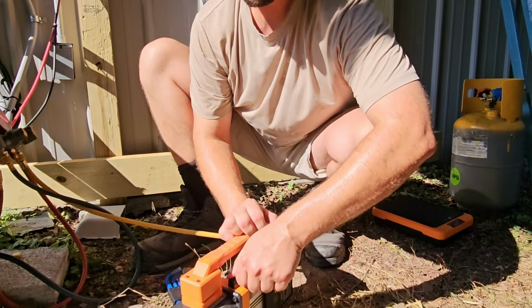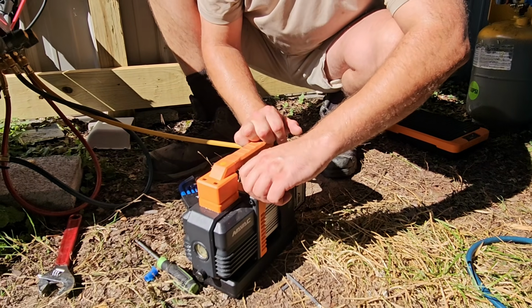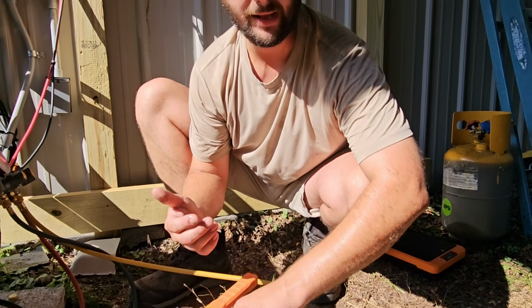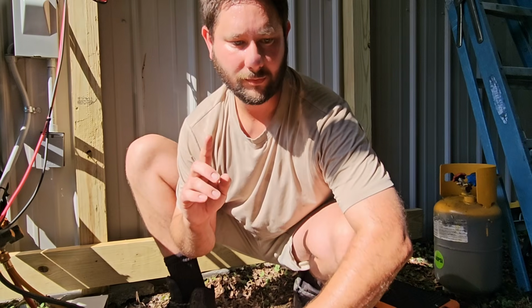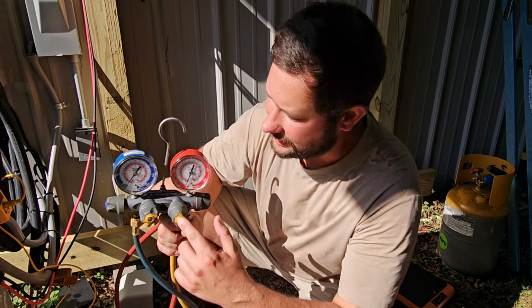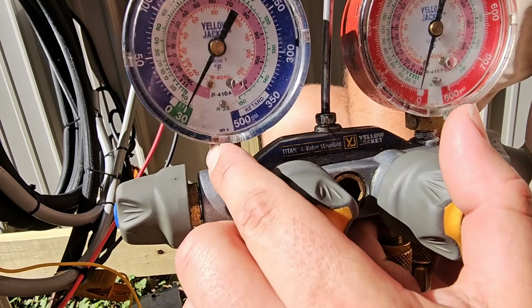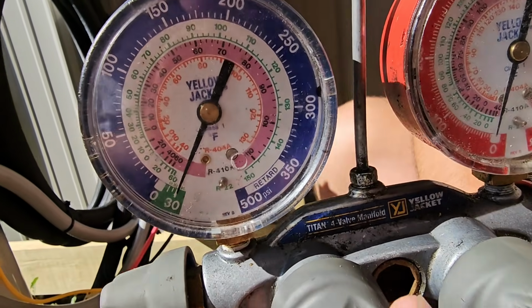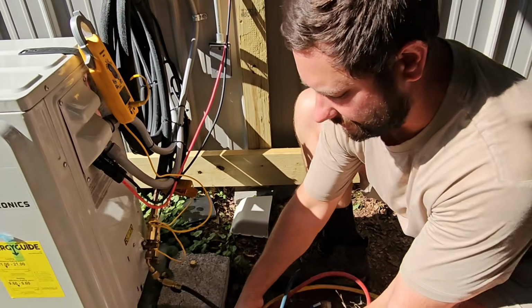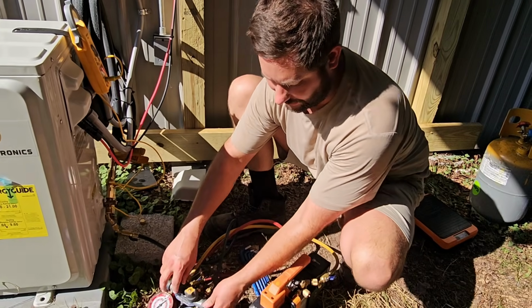So watch this. When I open this up and then close it, there's a change of sound, right? Listen. When we get a good vacuum, I'm going to show you that when you turn it off, there's going to be no sound from the valve going to the gauge. Now let's let this pull down for 15-20 minutes, and then we'll see what happens with our sound. Now, take a look at the gauges. It says exactly 30. We're going to close off our gauges and see if you hear a sound change. Listen.